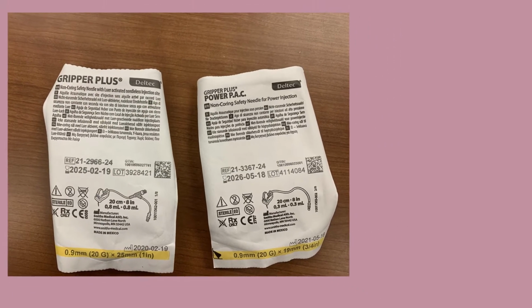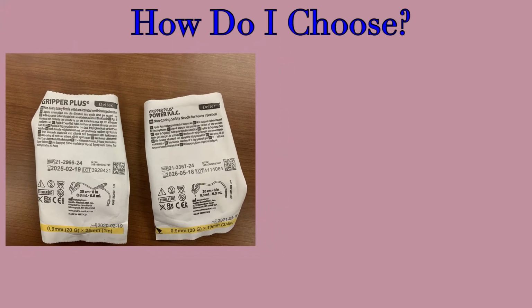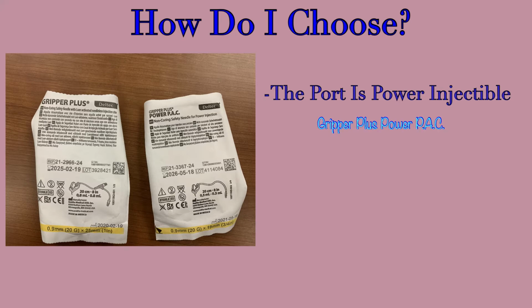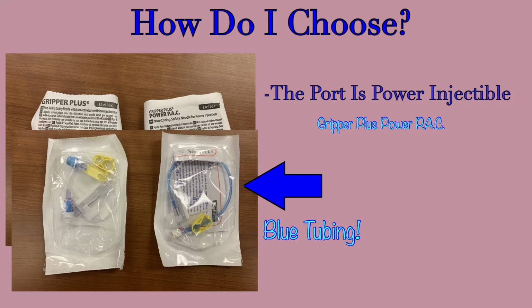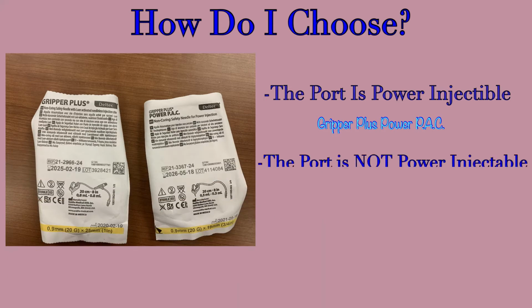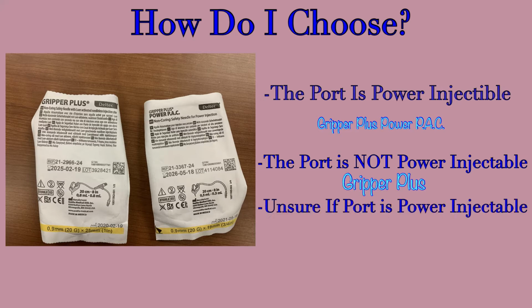Which brings us back to the question, which access device should I use to access this port? If you have verified that it is a power injectable port, use the Gripper Plus Power P.A.C.. This device has power injectable tubing that will hold up to increased pressure. The tubing of the Power P.A.C. is always blue, so you can tell which access device was used simply by looking at the tubing. If you have verified that it is not a power injectable implanted port, use the standard Gripper Plus. If you are unsure of what type of port it is, use the standard Gripper Plus.